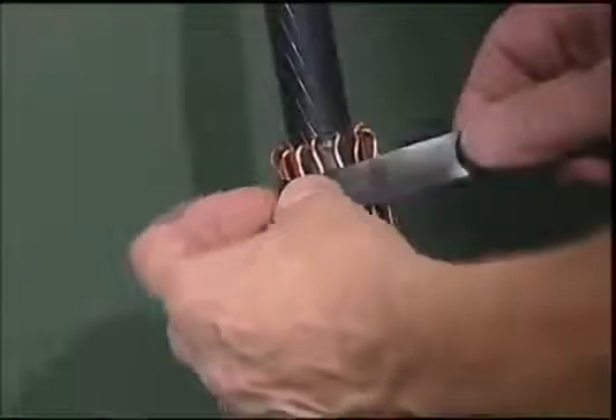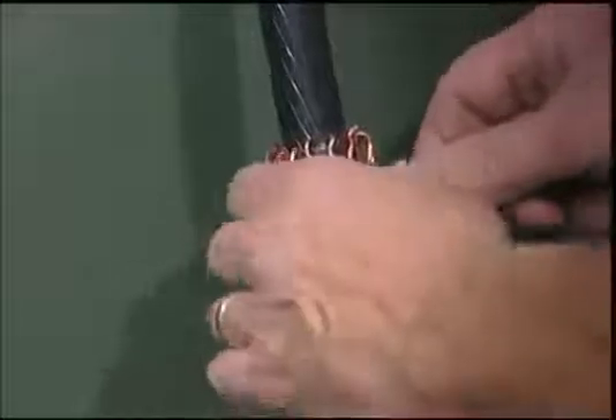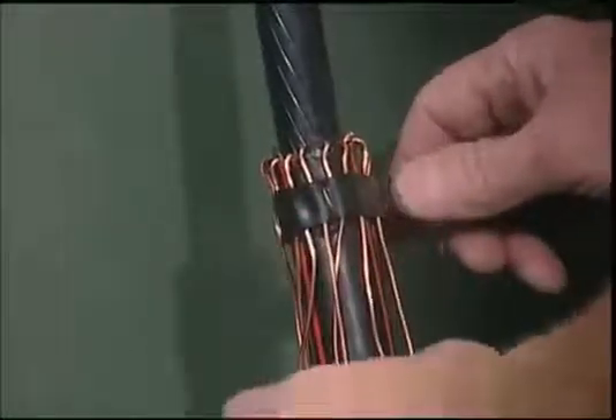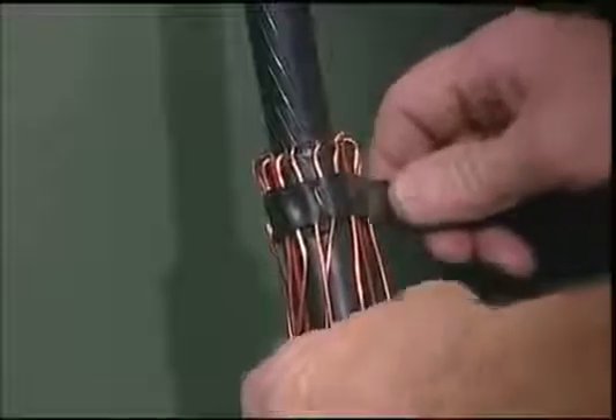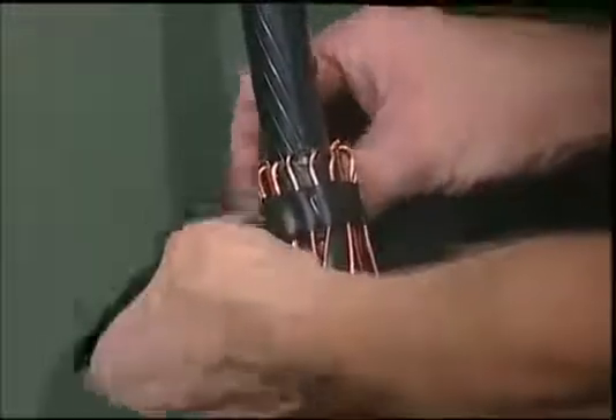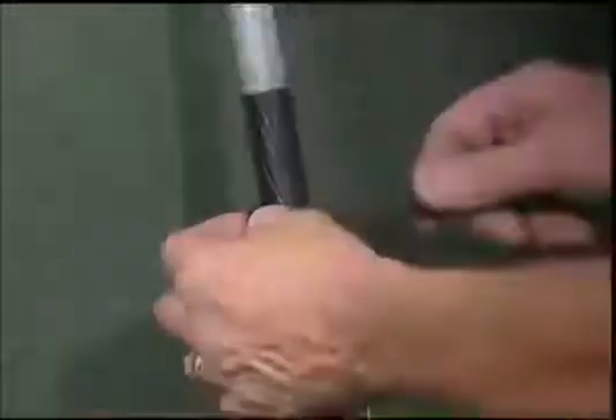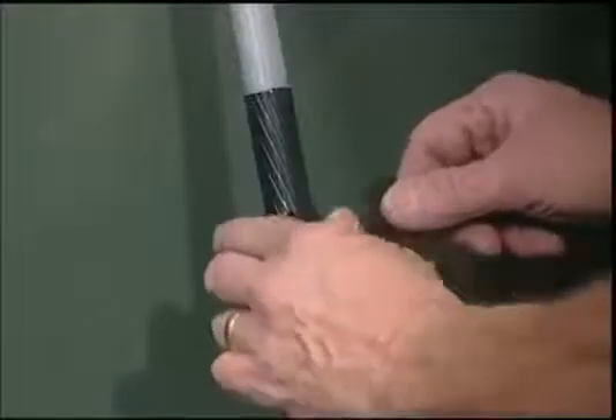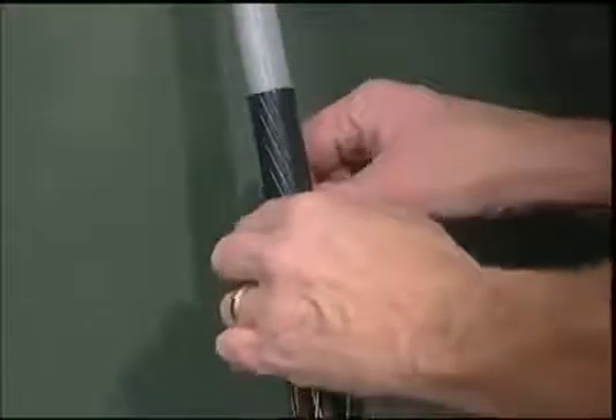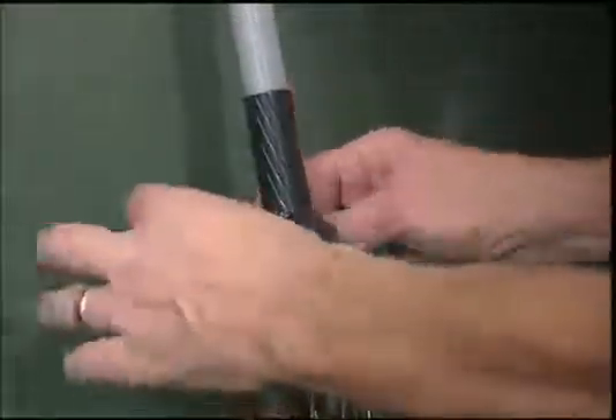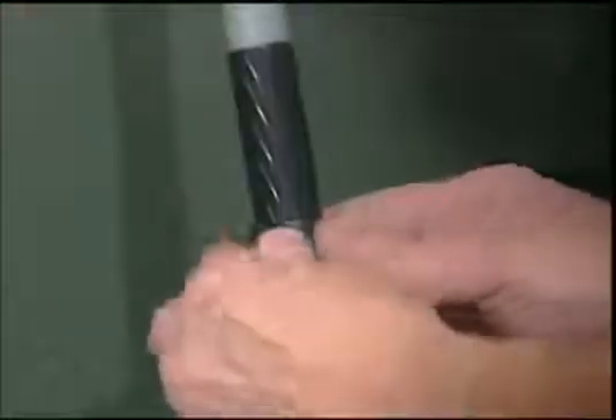Apply a second layer of mastic over the neutrals directly on top of the first layer. Now remember again, do not stretch the mastic when installing, but press tightly to fill in any voids. Apply a third layer of mastic, centering it on the transition point of the stripped back jacket and the insulation shield. Press it tightly into place, and again, don't stretch the mastic when you're installing it.